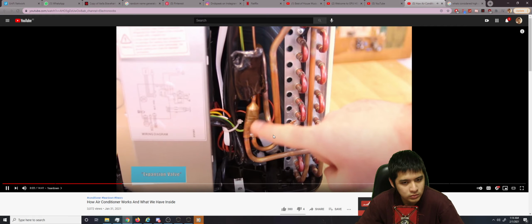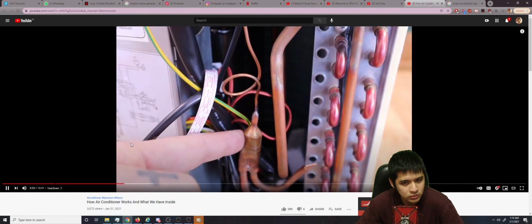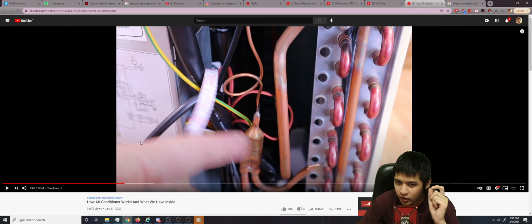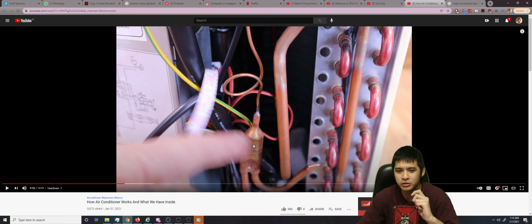On this copper tube circuit, we can also see this component here. And this is called an expansion valve. Okay, here's the thing. That's not called an expansion valve. That's a filter dryer and a capillary tube. It's called a metering device, not a TXV. TXV is its own thing. And this is either a check valve or a filter dryer inside. It varies, depends on manufacturer, especially for small units. I've seen a lot of these things that are empty, so I can't really say it's a filter dryer or something. In some cases, there are also these that don't even have anything in them, so I guess its only purpose is to make a connection. That's all.